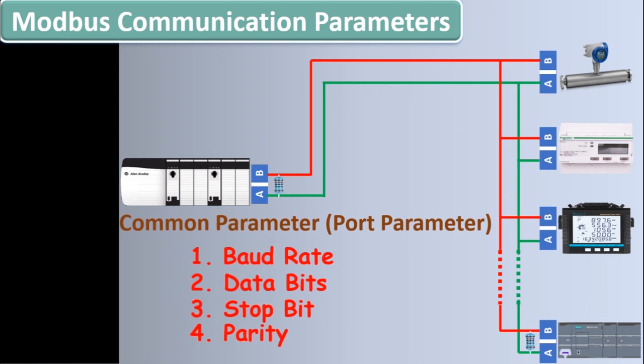Before going toward the Modbus parameters, let me summarize all the RS485 parameters for devices in the same communication network. We call these four parameters the common parameters or RS485 parameters of the devices — all these parameters must remain the same for all devices. For example: baud rate of 9600 bits per second, number of data bits as 8, stop bit as 1, parity as none. Usually these are the default values, but they can be changed.